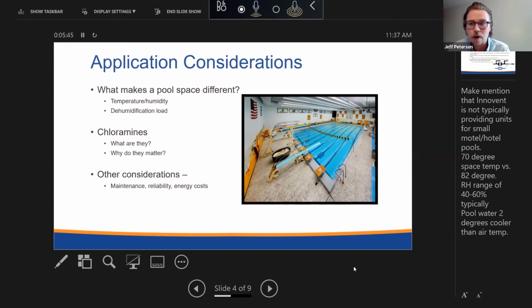Some customers ask, well, why aren't we controlling to like 70 degrees? If you've got coaches in there, you don't want them to be too hot. And the reason is if you have 70-degree air temp and 80-degree water, the evaporation rate is going to go through the roof. So that's going to really drive up the required size of the HVAC equipment, and it's also going to increase the water load. You're going to have to be constantly adding more and more water to that pool. So those are some things to keep in mind.